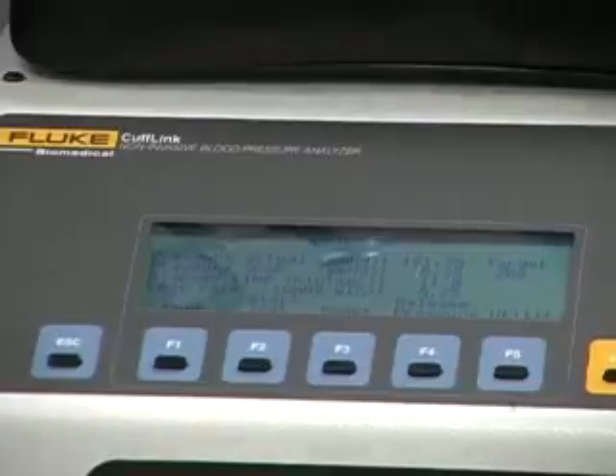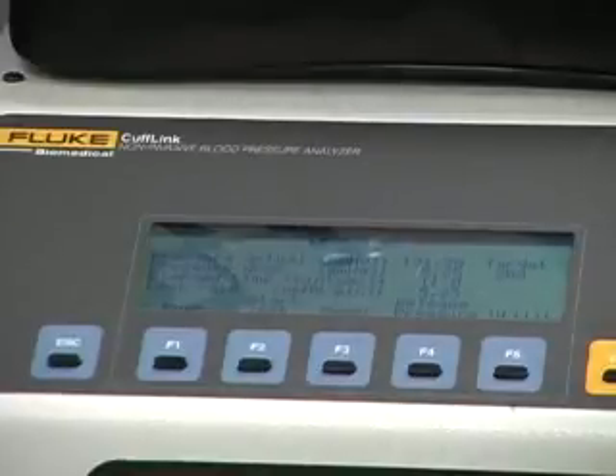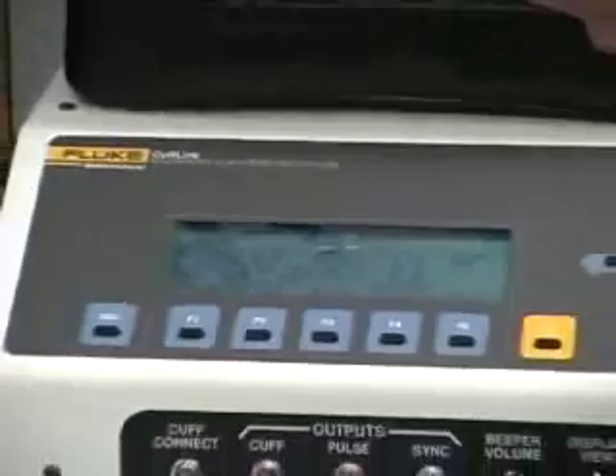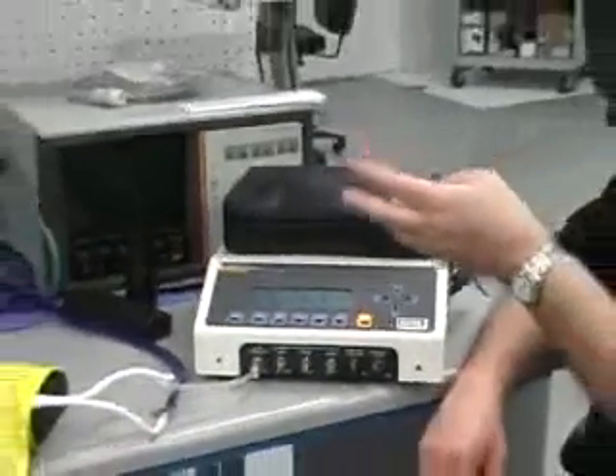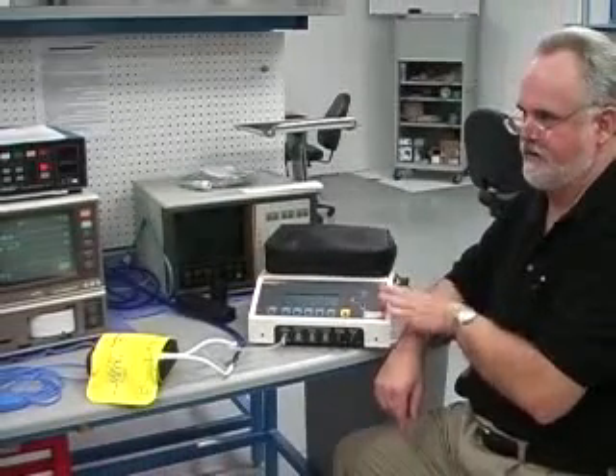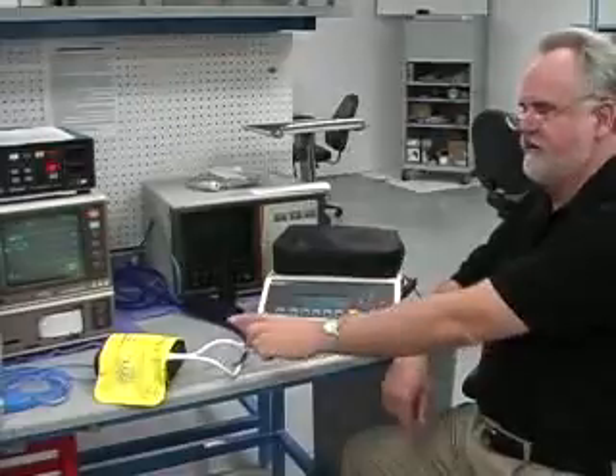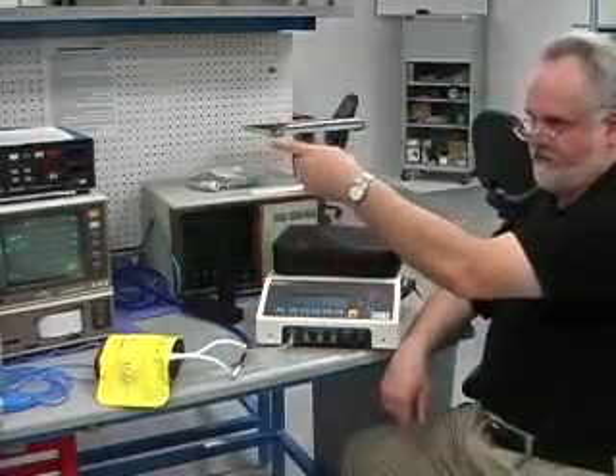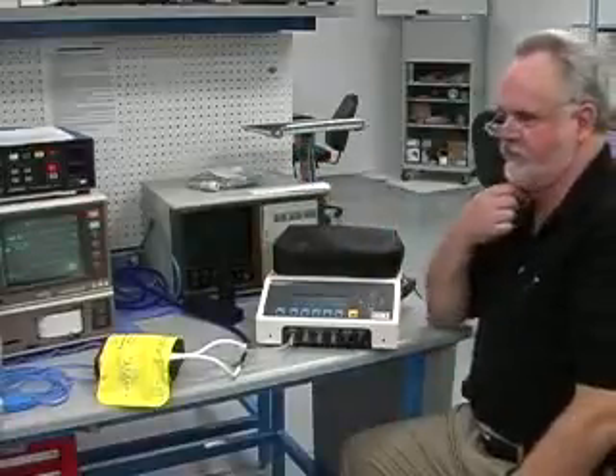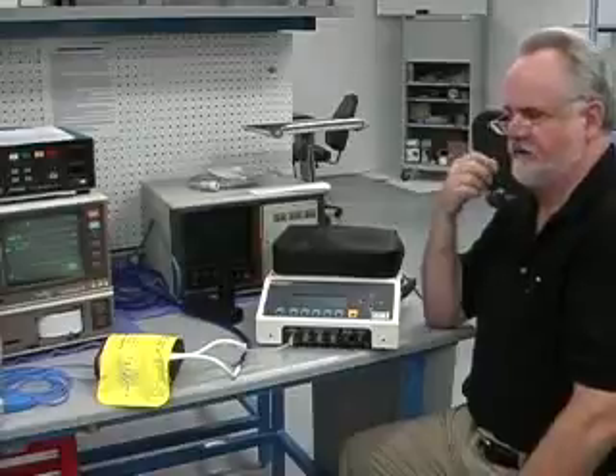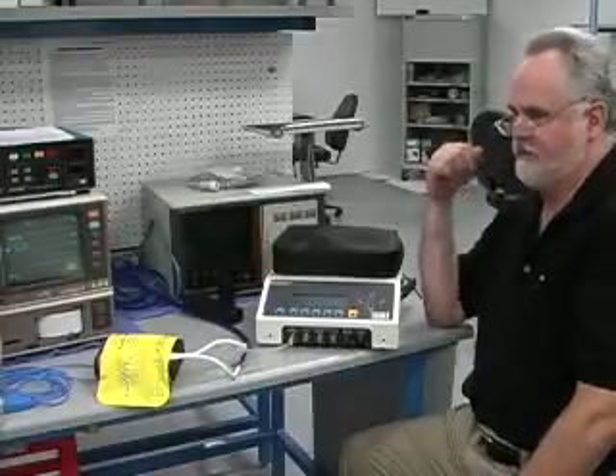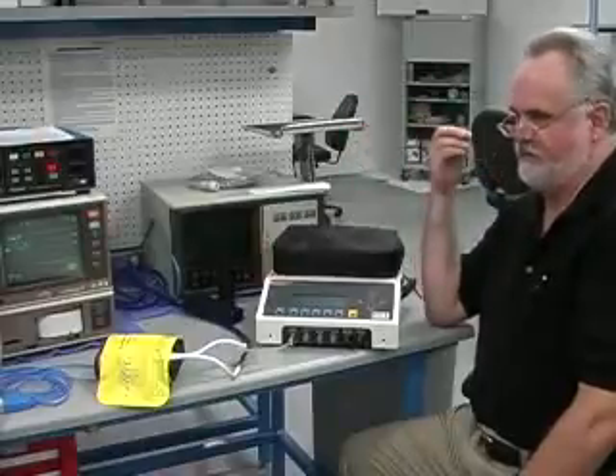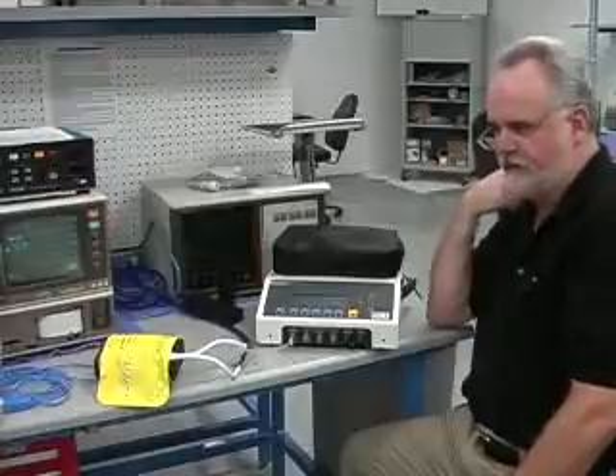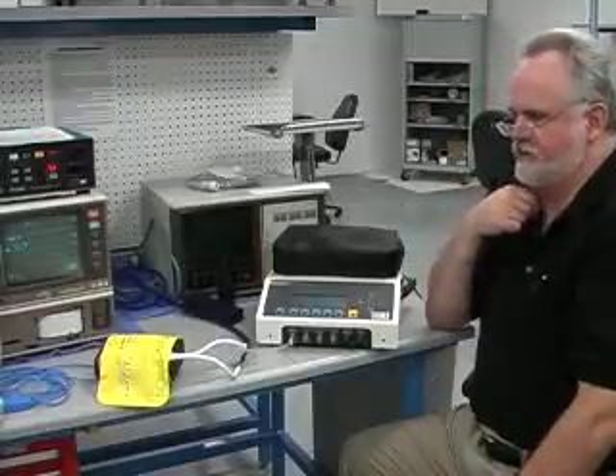So again, making sure the NIBP device does have this type of diagnostic mode. What you might find out too is that in some cases when you're making these tests, the NIBP monitor has its own leak rates built into it and its own diagnostics. So if that's the case, you can use the Cufflink in its own digital manometer mode where you're monitoring the pressure here, and you can actually then run the tests using the device. I know many of them do this. I know the Philips do. Medical Data Electronics, they actually run those tests automatically, and they will do the static pressure checks and also the pop-off test, and the leakage, manometer and pop-off tests can be done with those devices directly.